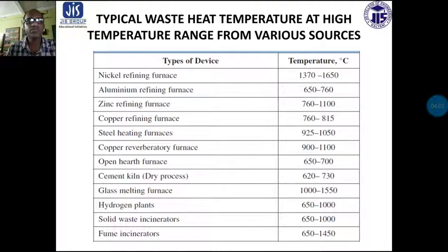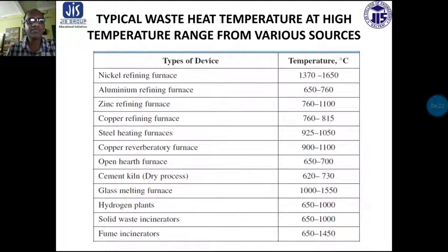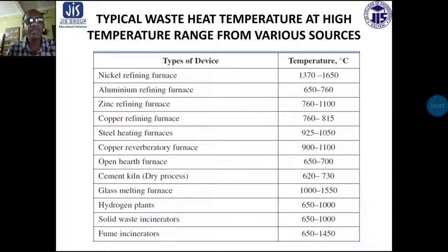Open hearth furnace 650 to 700 degree centigrade. Dry process cement kiln temperature ranges 620 to 730 degree centigrade. Glass melting furnace 1000 to 1550 degree centigrade. Hydrogen plants 650 to 1000 degree centigrade. Solid waste incinerators 650 to 1000 degree centigrade. Fume incinerators 650 to 1450 degree centigrade. These are the typical high temperature waste heat sources from various processes; if we can utilize this heat through waste heat recovery devices we can maximize fuel economy.